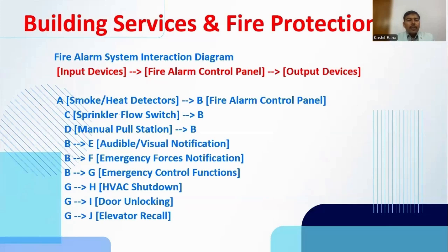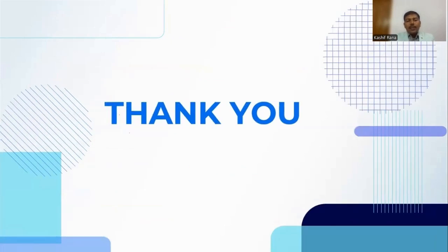For more clarity, the input devices include any detection system like smoke, heat, flame, or other detectors, sprinkler flow switches, and manual pull stations. They initiate the signal and pass it to the fire alarm control panel. Then the fire alarm control panel gives instructions for audible and visual notification, emergency forces notification, and emergency control functions like HVAC shutdown, door unlocking, and elevator recall. This is all about today's session. We learned how people can be notified and how they can safely and smartly evacuate from the floor and from the building.